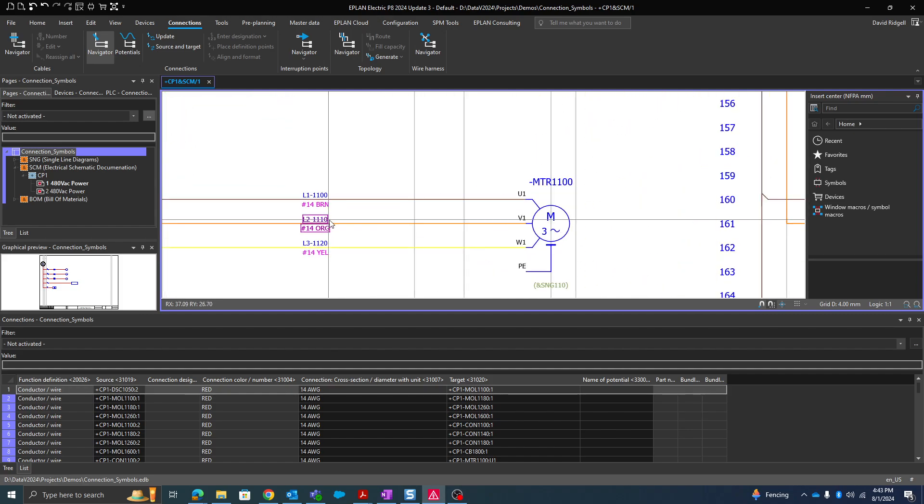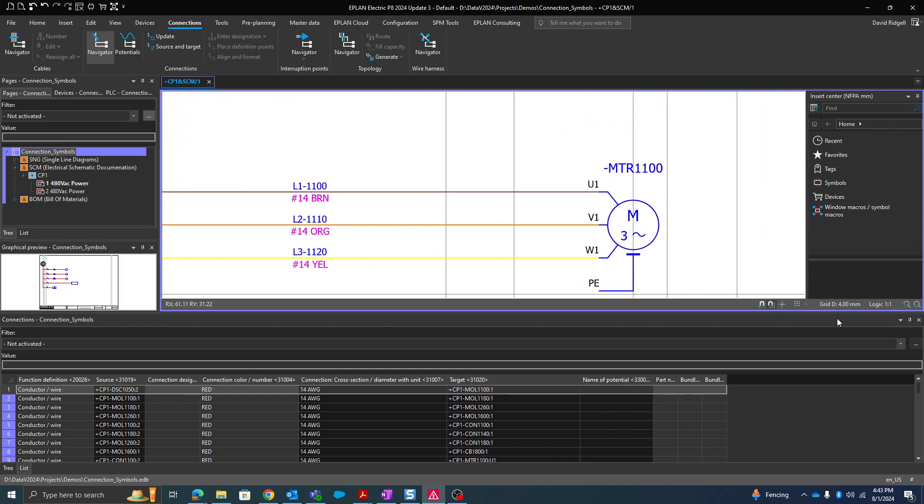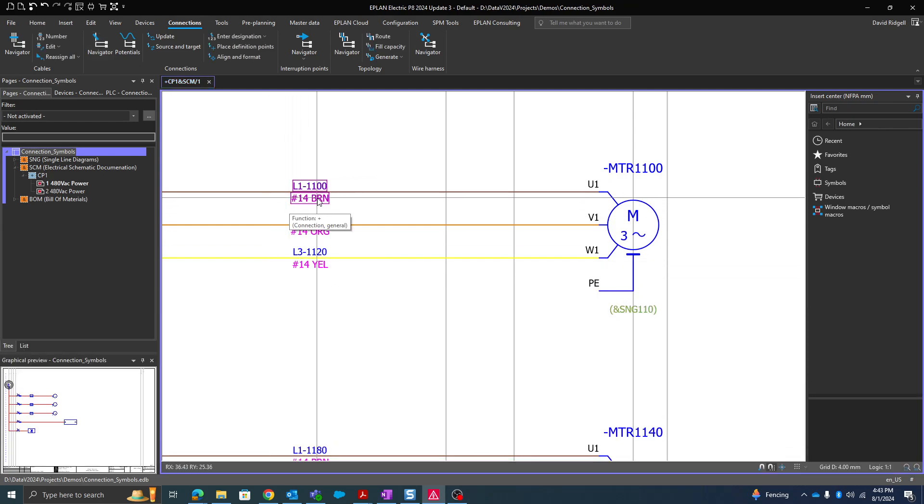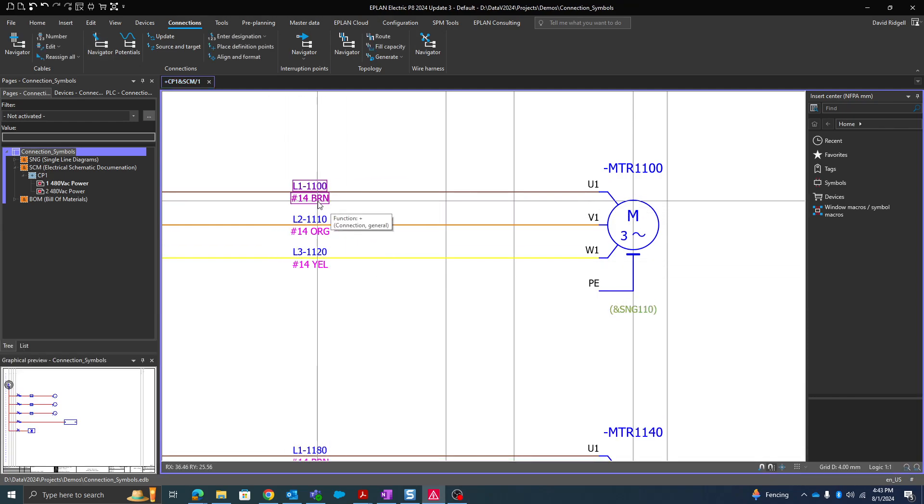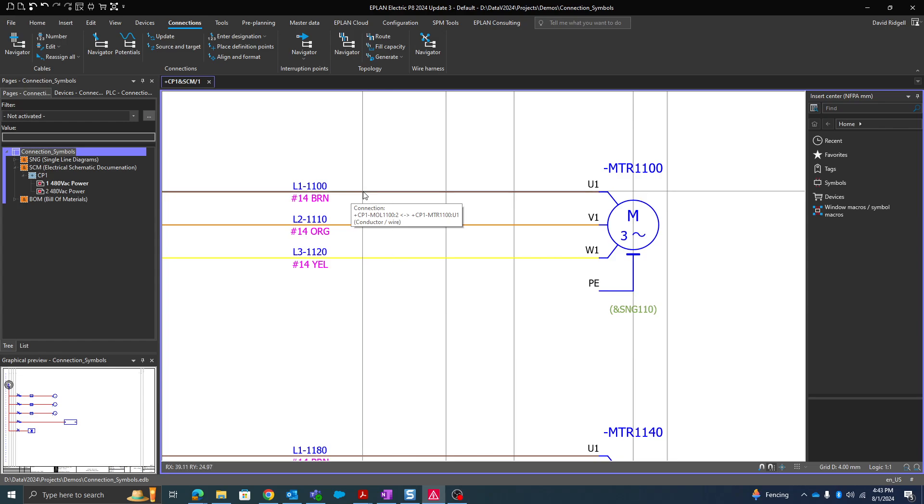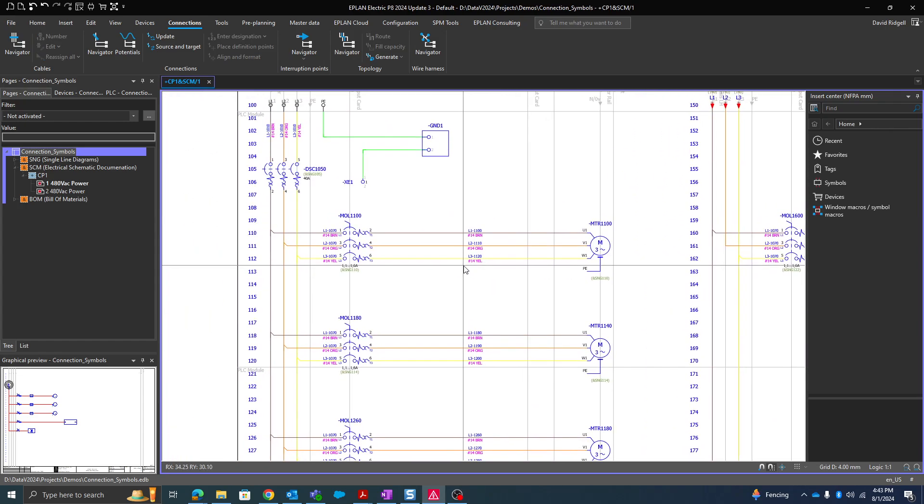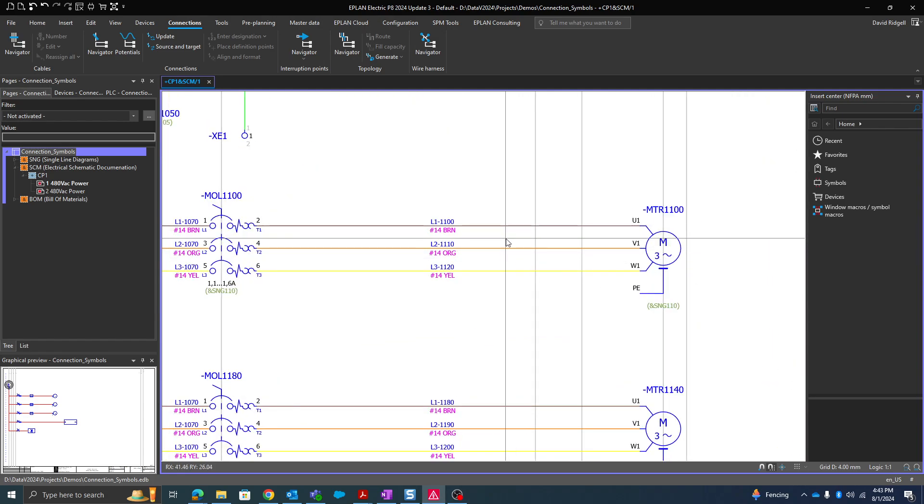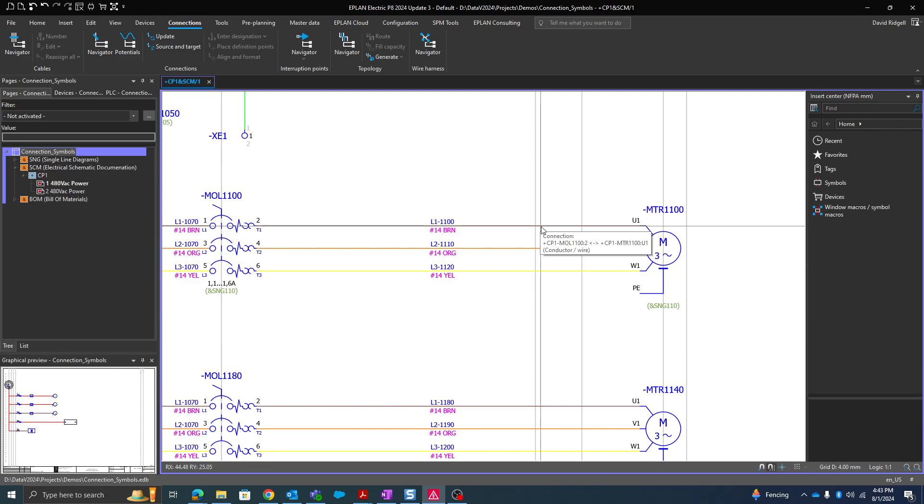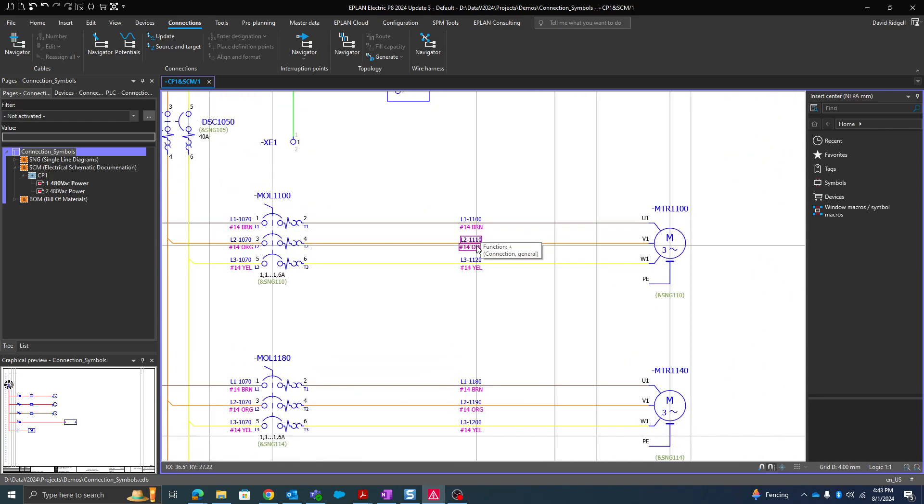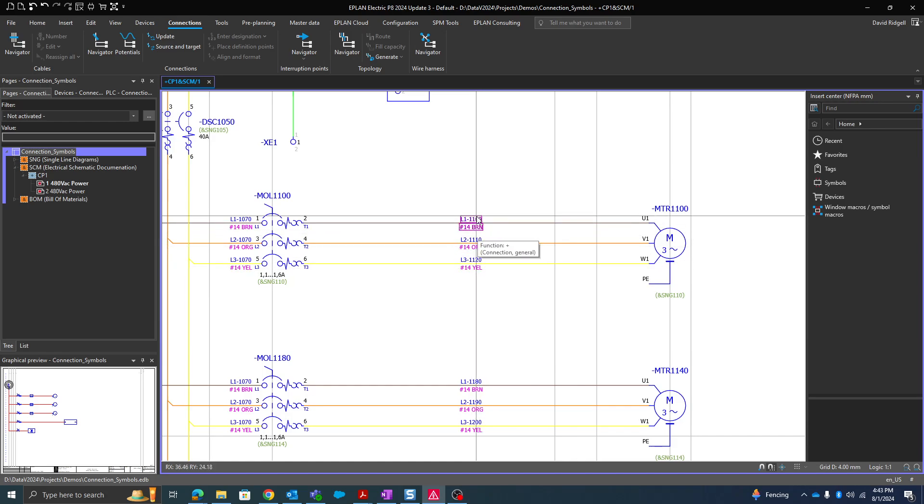We can display at the connection definition points not only its own native properties, but also the properties of the actual connection. Why is this important? Because we can actually get these properties of color and size from the potential or the project settings. In this example, none of these have actually had their color and size defined. If you go into the properties of one of those definition points, you'll see that the color and cross section is empty. The reason for that is under display, I'm displaying the actual properties of the connection.